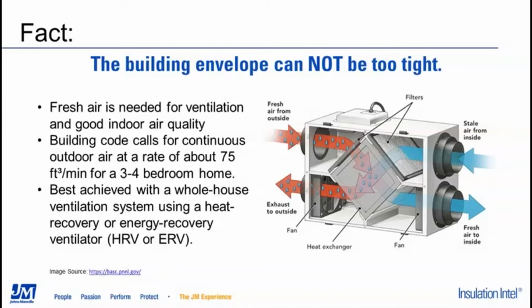These are devices that bring in fresh air and exhaust stale air. The additional benefit they bring is that the exhausted air and the fresh air pass through a heat exchanger, which lets the incoming air be tempered by the exhausting air. The difference between an ERV and an HRV is that an HRV only exchanges heat between the air streams, while an ERV also exchanges humidity. An ERV is usually recommended in more humid climates, but that could also be used anywhere. HRVs and ERVs help reduce the energy impact of bringing outdoor air into the building.